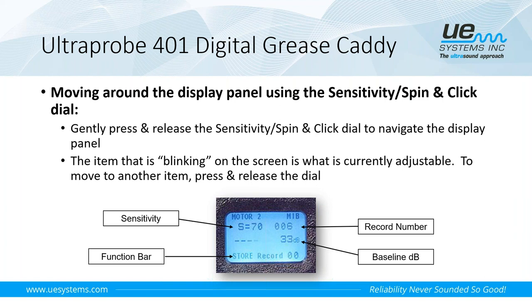All right, here's a closer look at the display. We'll start over here with the sensitivity, the top left, where we have this S equals number. What the sensitivity is, and this is available on all of our instruments, is basically a gain. When I turn up the sensitivity, I'm increasing the amount of power that goes to those piezoelectric crystals inside of the different modules.